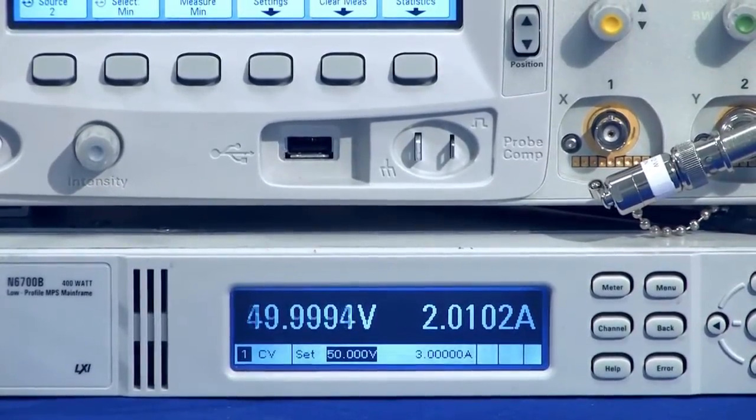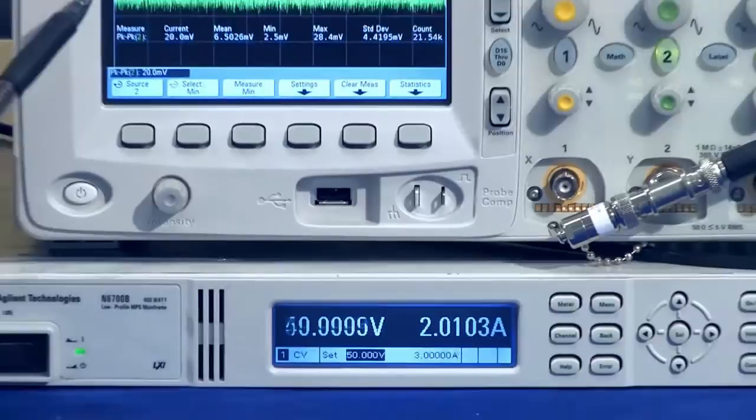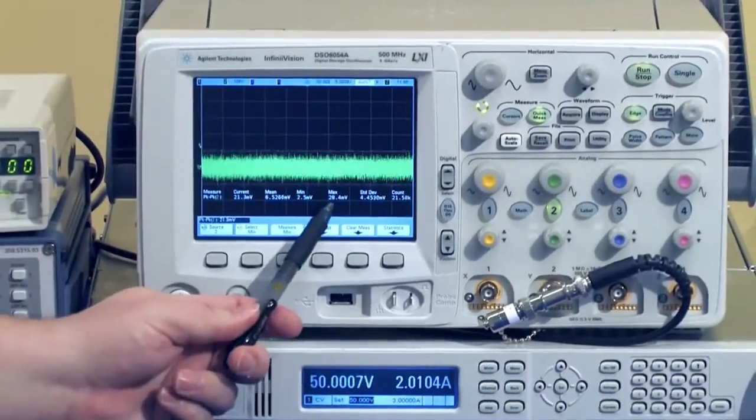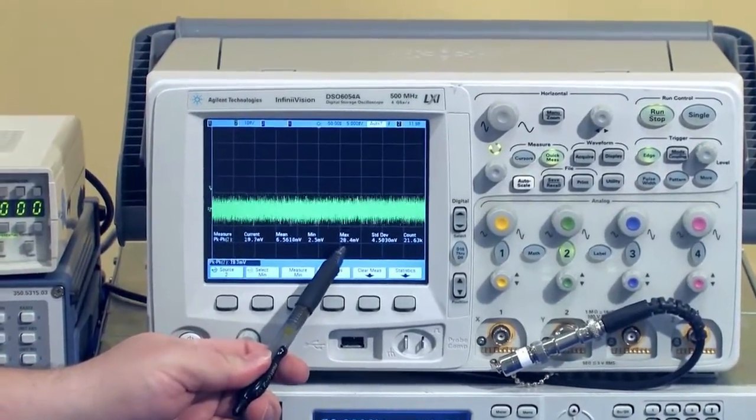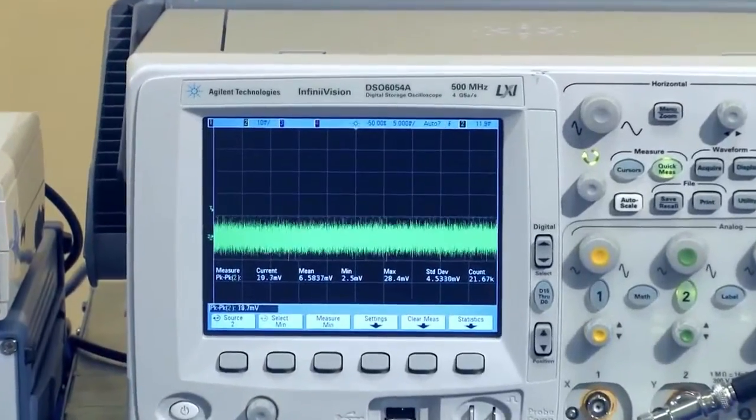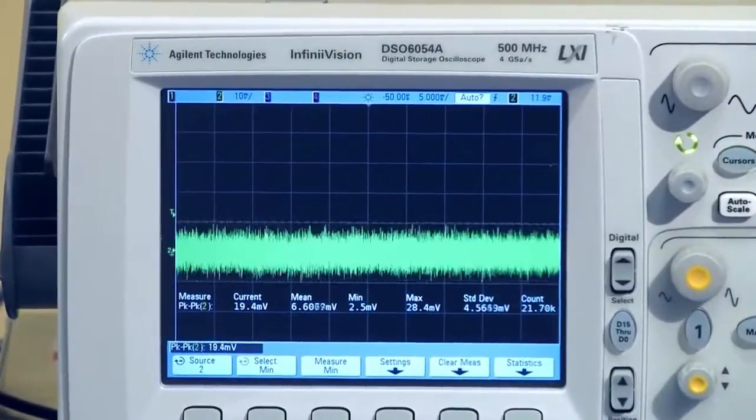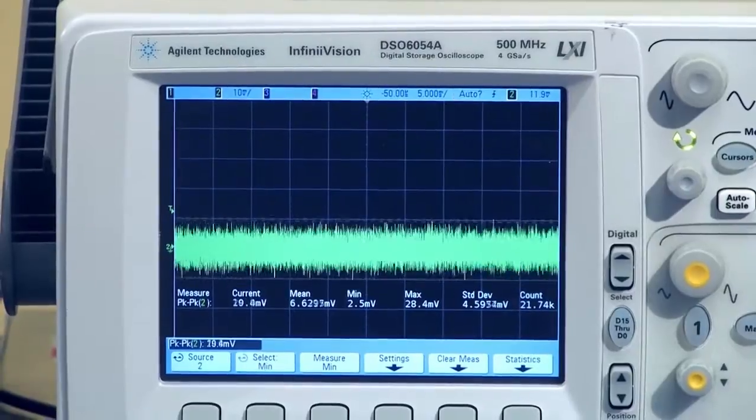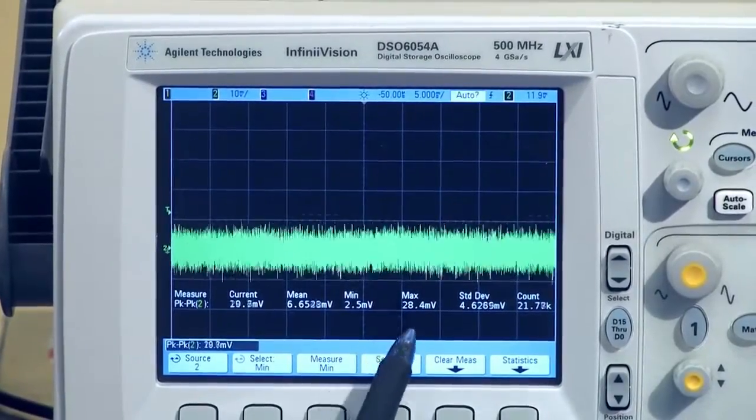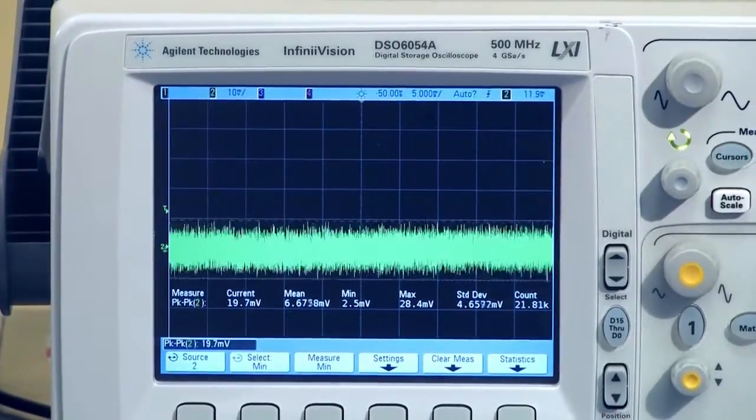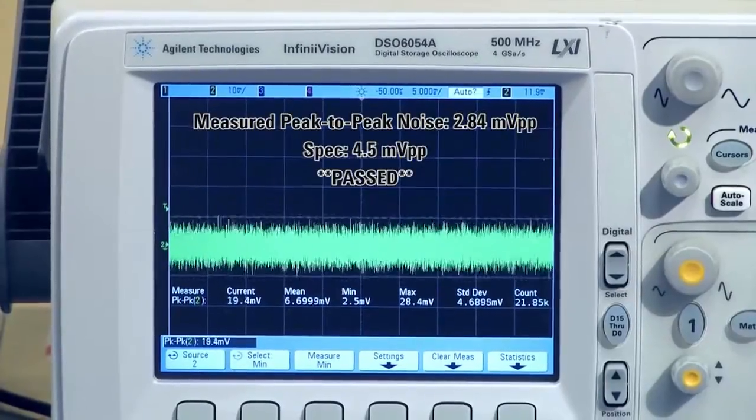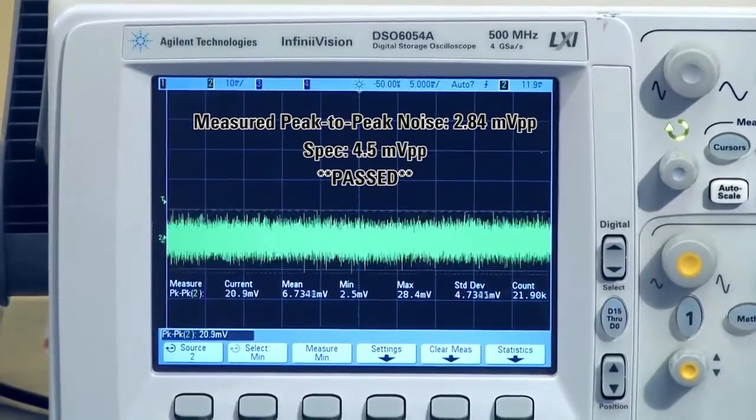Looking at the scope, you can see that the maximum peak-to-peak measured was 28.4 millivolts. Our differential amplifier is set to times 10, so you take the 28.4 millivolts divided by 10 to get 2.84 millivolts. Our specification is 4.5 millivolts, so this unit is in spec.